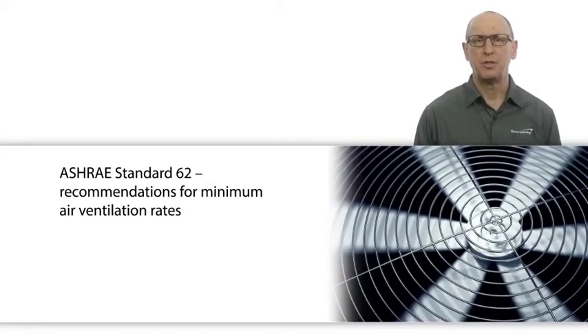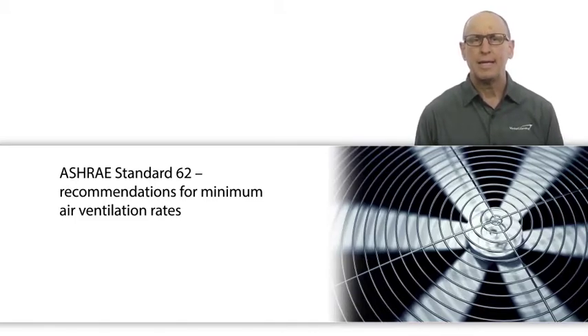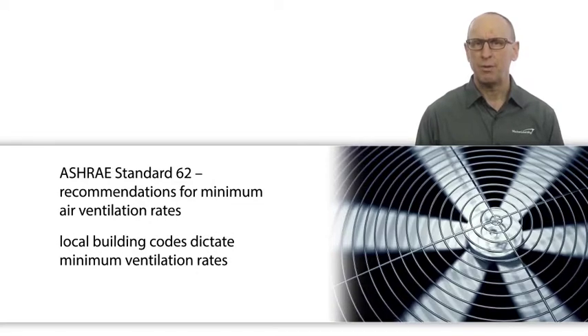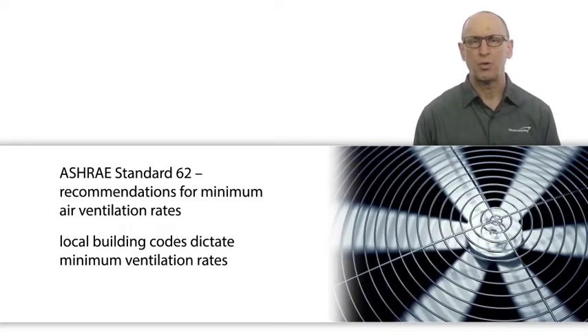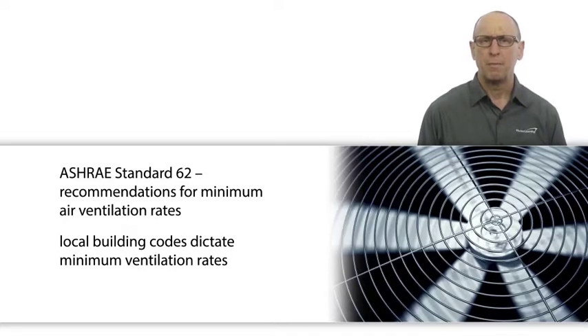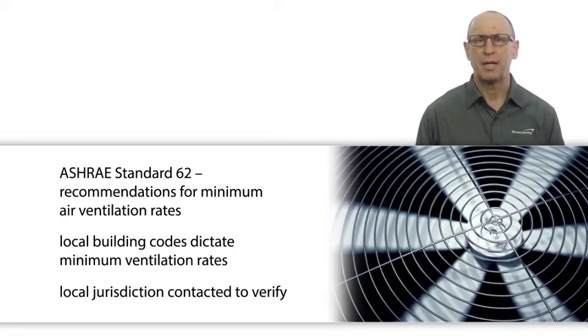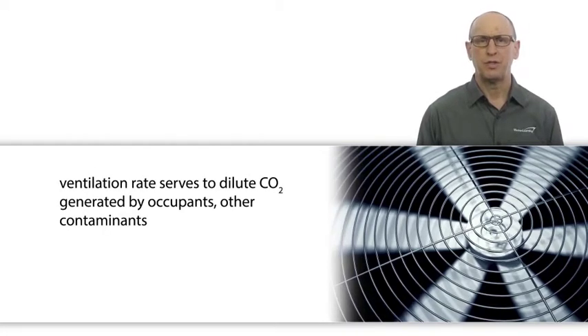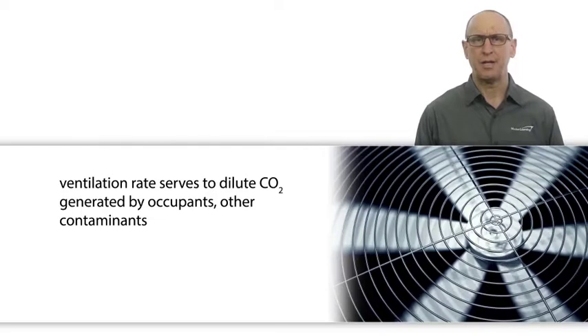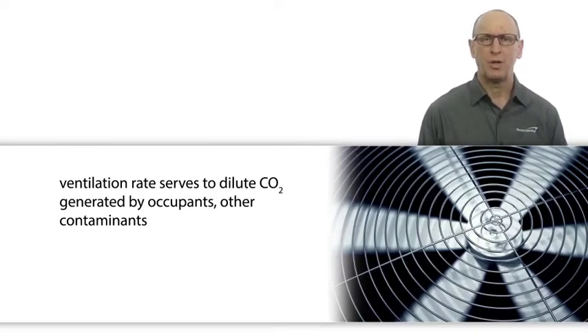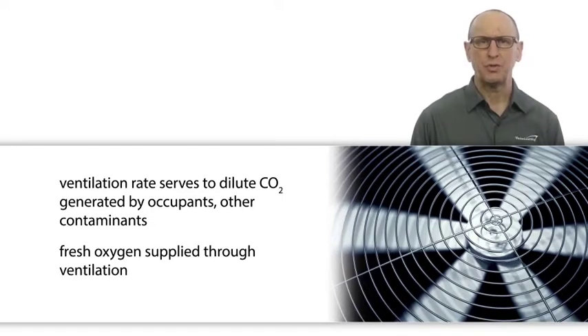ASHRAE Standard 62 provides recommendations for minimum air ventilation rates per person in occupied spaces. In addition, local building codes may dictate minimum ventilation rates for commercial buildings and work environments. The building departments in the local jurisdiction should be contacted to verify this. The ventilation rate serves to dilute any carbon dioxide in the space generated by the occupants, as well as other contaminants that might be generated in the space. Fresh oxygen is also supplied for the occupants through fresh air ventilation.